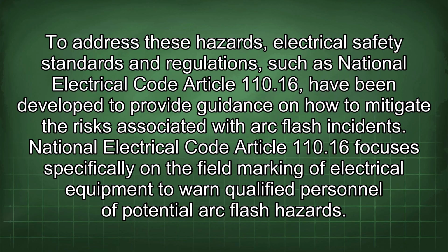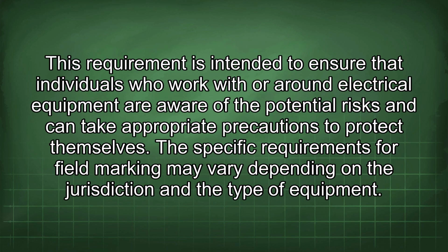National Electrical Code Article 110.16 focuses specifically on the field marking of electrical equipment to warn qualified personnel of potential arc flash hazards. This requirement is intended to ensure that individuals who work with or around electrical equipment are aware of the potential risks and can take appropriate precautions to protect themselves.